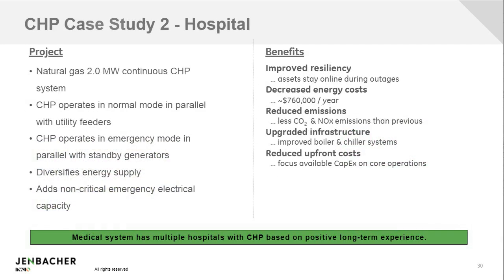The second case study is another hospital. This one is in the U.S., and the CHP portion of this particular project is a natural gas 2 megawatt continuous CHP system. It operates in 2 modes. The first mode is run normally parallel to the utility. There's multiple utility feeders coming into this hospital, so it's normally running parallel to them. However, if the utility does go down for whatever reason, the standby generators come up to speed, and then the CHP operates in parallel with the standby generators.